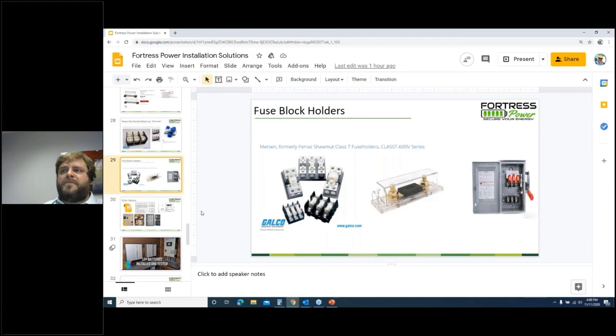And so some installers have arc faulted during installation, and then they have to open up our batteries and do some field servicing, or some of them mail the batteries back to us and we'll service them here. To avoid having to get inside your battery to do servicing, you may want to add fuse blocks and some external overcurrent fuse protection. We've taken it out of our installation manual because if you put something in the installation manual and it's an optional step rather than a mandatory step, not all inspectors will view it as an optional step. But by taking it out of the installation manual, that does also remove with it the fact that it is a good idea to install additional overcurrent protection.